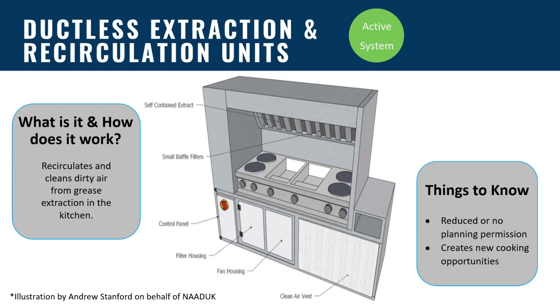Ductless extraction and recirculation units have come on the market. They recirculate and clean the dirty air from grease extraction in the kitchen. The systems remove moisture, steam, smoke, grease and odour. What's great about these systems is that they're suited to spaces and layouts which normally wouldn't accommodate a kitchen in a commercial space. So places like airports, railways, listed buildings, basement kitchens, kiosks, island sites, and more. Because they require reduced or no planning permission, it's easy to have a change of use. They don't require external ductwork or a route to atmosphere.